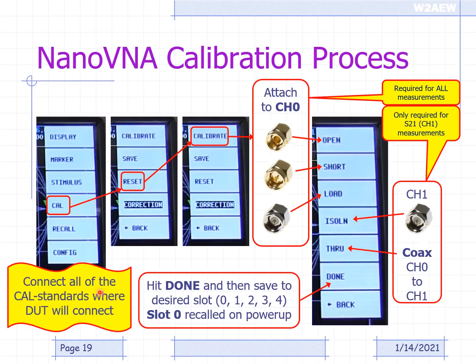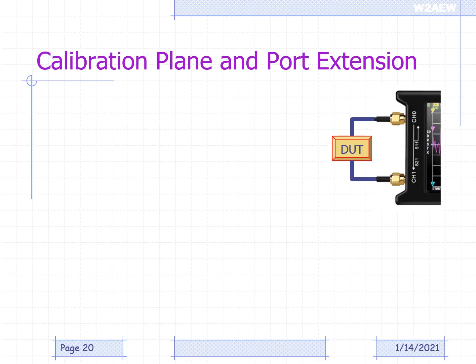Connect all of the CAL standards when possible to the same place where your device under test will connect. By doing that, you can ensure that you've established that measurement plane right at your device interface ports. Now, in those cases where you can't connect exactly to where your device would connect, to be able to remove the phase of those interconnections, you might need to use an adapter or some other length of interconnect out to where your device is. So you can use this feature called port extension to essentially slide that measurement plane back and forth to establish it at your particular spot that you need on the DUT.